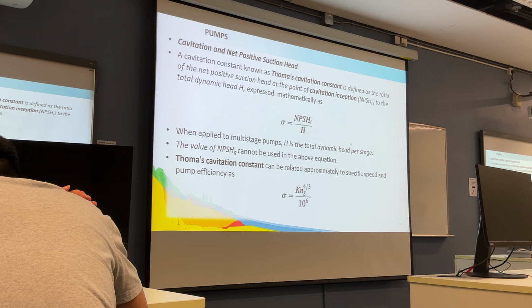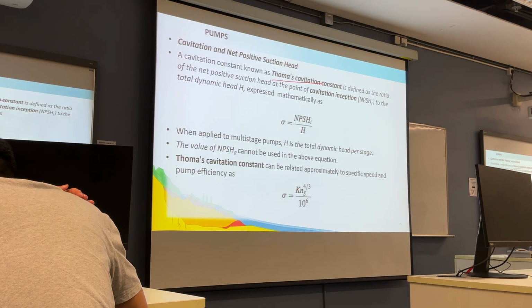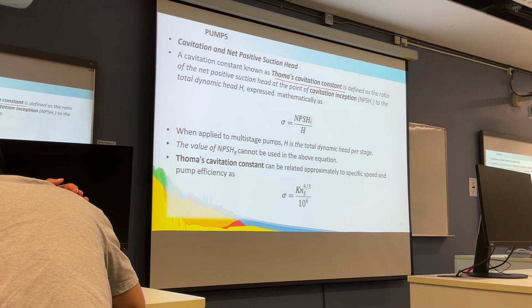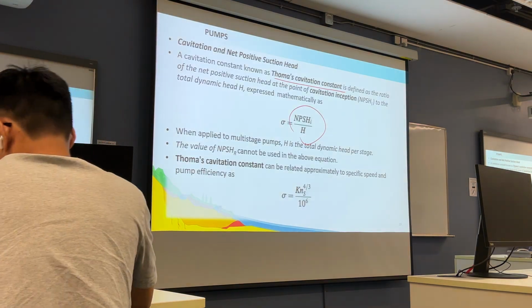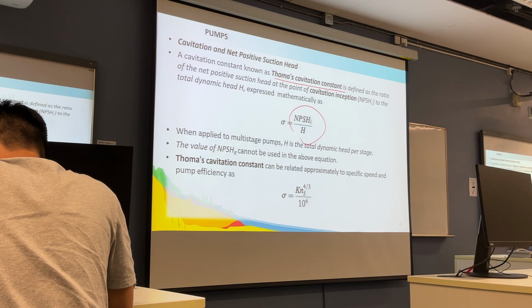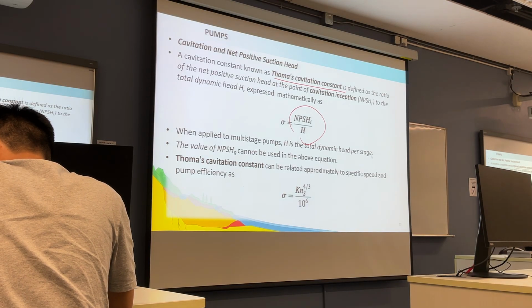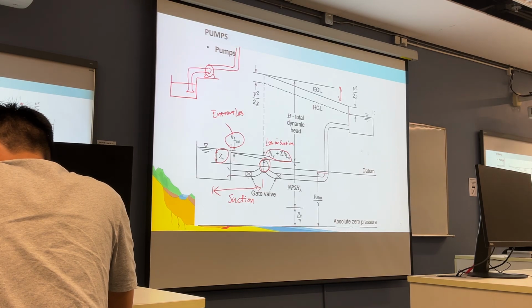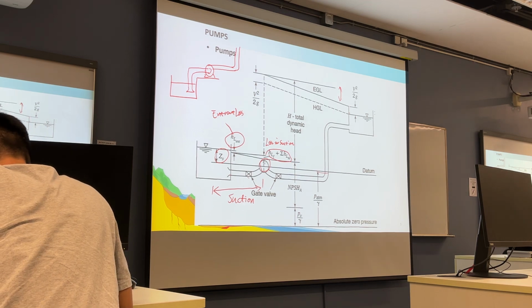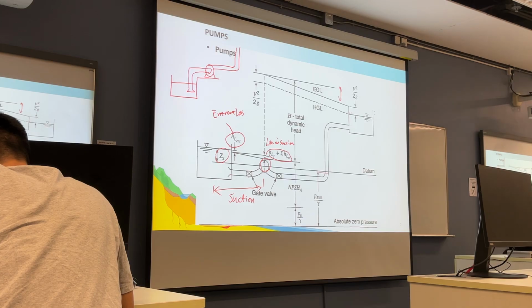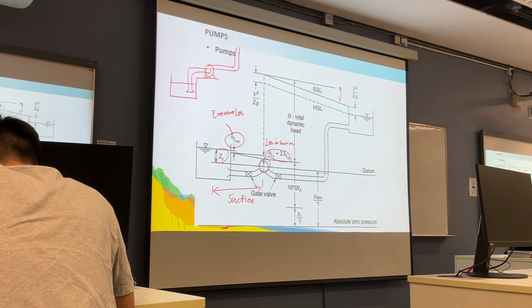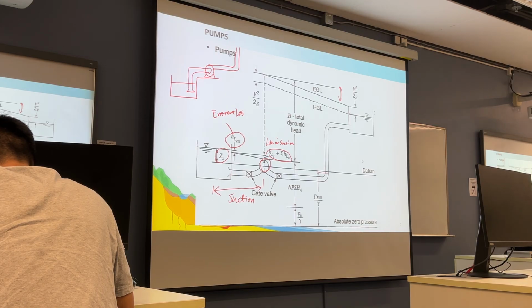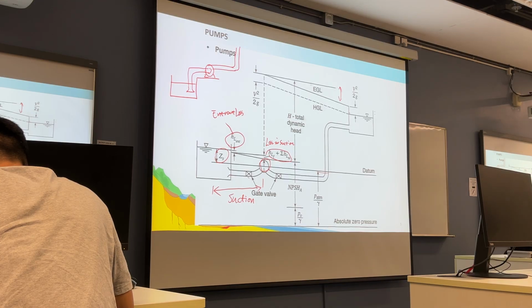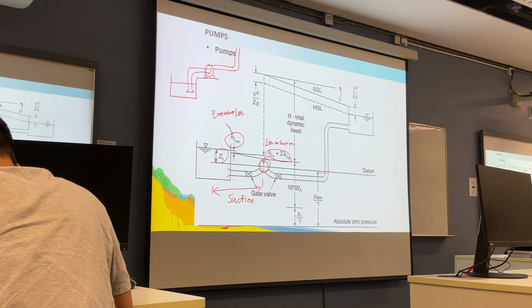Now, another one is the calculation of the Thoma cavitation constant, by dividing the cavitation inception over the total dynamic head per stage. If it is a single stage, the total dynamic head is talking about this one, from the pump eye to the secondary reservoir surface. This is the total dynamic head. That means the pump head needs to provide to overcome the head loss in the downstream and also the elevation difference.